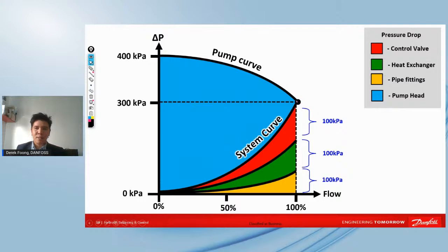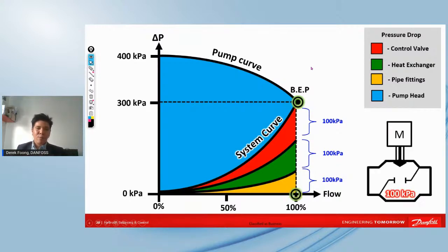And of course, this is where you get the impellers to be compared, whichever will give you the right capacity and also the right operating point, or you call it the best efficiency point, abbreviated here as BOP or BEP. So now with the pump curve and system curve defined, and this is based on full load, all right? So what happens if the control valve closes, like we see during part load?